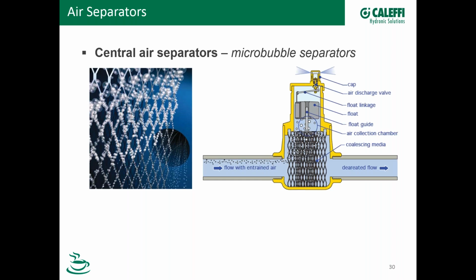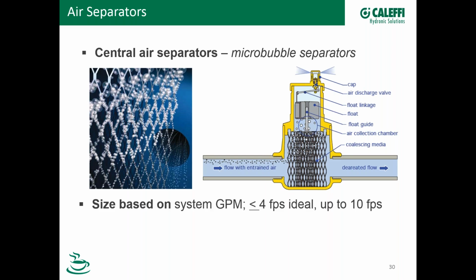If we look at a cutaway, here's what that might look like. As your flow comes in with the entrained air, the coalescing element is in that flow path. You can see the increase in cross-sectional area there where the water slows down and those bubbles coalesce and then bubble up into the air vent and then get discharged out of the cap. So that's a nice cutaway that illustrates how that works.